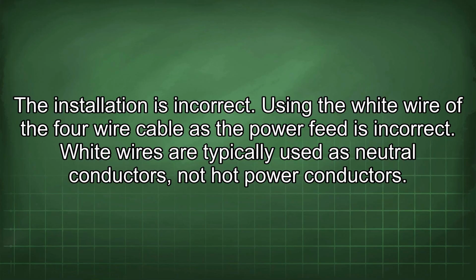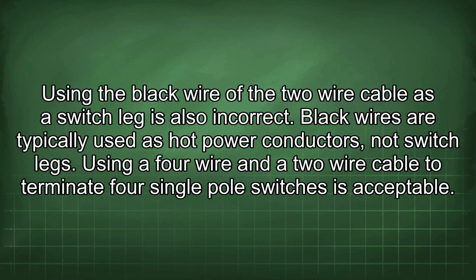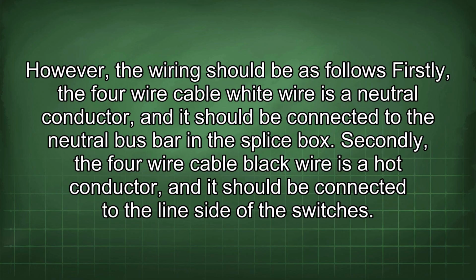The installation is incorrect. Using the white wire of the 4-wire cable as the power feed is incorrect. White wires are typically used as neutral conductors, not hot power conductors. Using the black wire of the 2-wire cable as a switch leg is also incorrect. Black wires are typically used as hot power conductors, not switch legs. Using a 4-wire and a 2-wire cable to terminate 4 single-pole switches is acceptable. However, the wiring should be as follows.